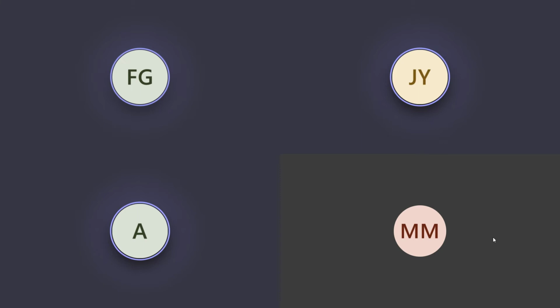Do we have data on the CFM rating of the vertical flow fan for every model? For the CFM rating, yes, we have that data, the airflow. But frankly speaking, this data is calculated by our engineers who build the units, and we didn't test it. But it's also okay, because normally the calculation is bigger than the true airflow, and it is enough for you to consider for indoor installation or installation with ducting. For airflow, we can send it.